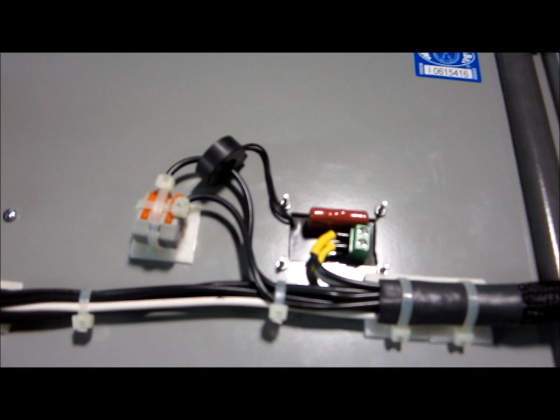Coming in, here's the back of the panel meter: simple voltage in, 120 volts in, 115 nominal. I've also got this clamp-on, pass-through transducer that measures amperage, and I just nipped it and have a plug-in toggle connector which helps with passing that wire up. That's tied to that.